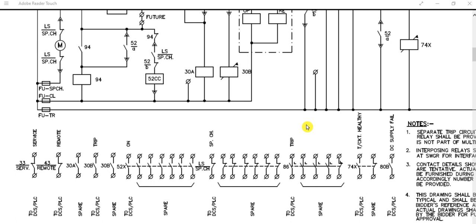This is the 33 in-service position contact. This is one of the breaker auxiliary contacts. This contact is used to indicate that the circuit breaker is in service position, and this signal is going to the PLC or any remote panel. The wiring should be done from this switchgear terminal up to the DCS panel. This contact represents the circuit breaker in-service position.